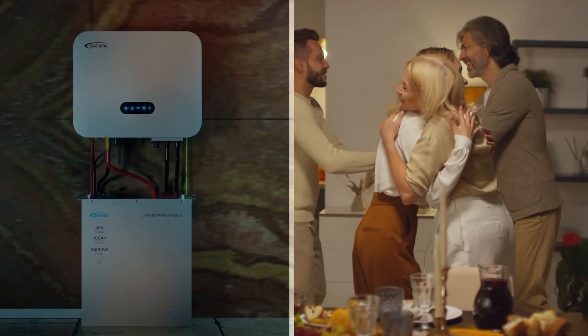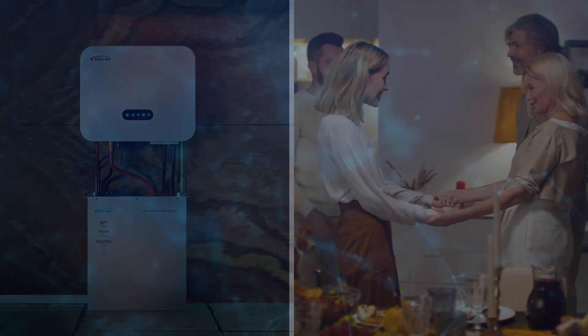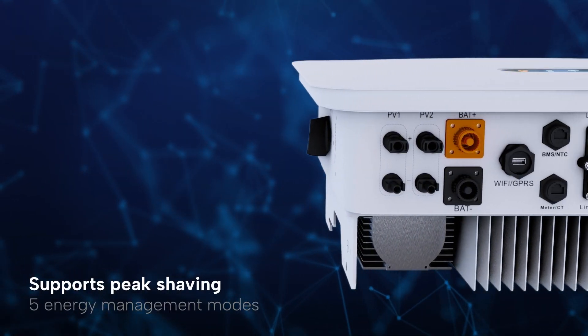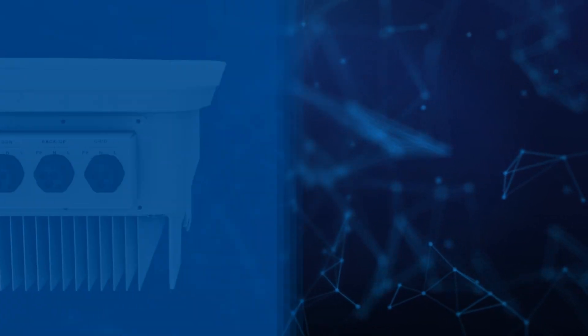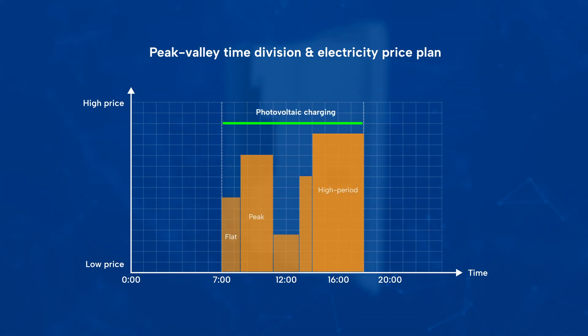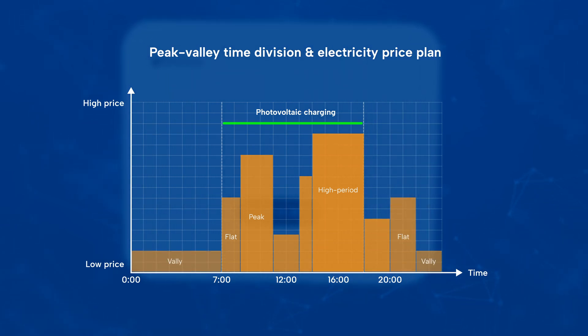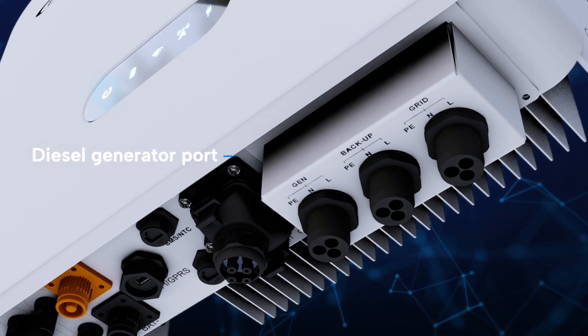When sunlight is plentiful during the day, ELS draws power from the solar panels; at night, ELS draws energy from the battery to supply power to the load. Peak shaving mode is a power management strategy that allows users to set power limits based on their demand — during peak consumption, ELS restricts grid draw with the shortfall supplied by photovoltaics and batteries. When power consumption is low, the ELS system purchases electricity from the grid to charge the battery, maximizing electricity cost savings.